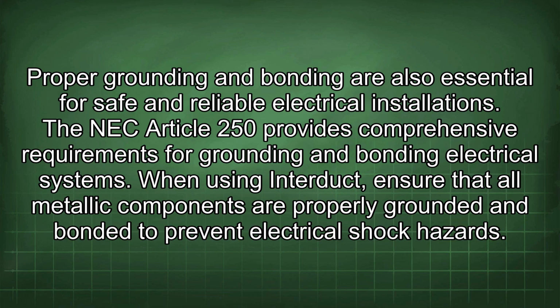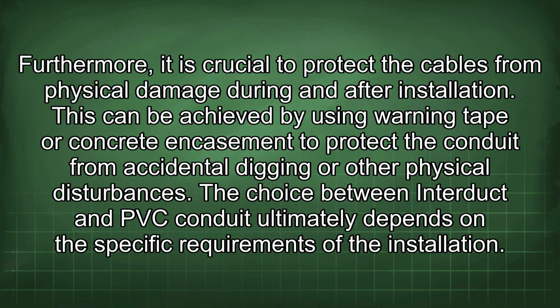The NEC Article 250 provides comprehensive requirements for grounding and bonding electrical systems. When using Interduct, ensure that all metallic components are properly grounded and bonded to prevent electrical shock hazards. Furthermore, it is crucial to protect the cables from physical damage during and after installation.